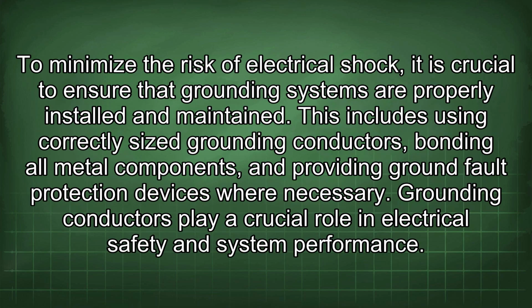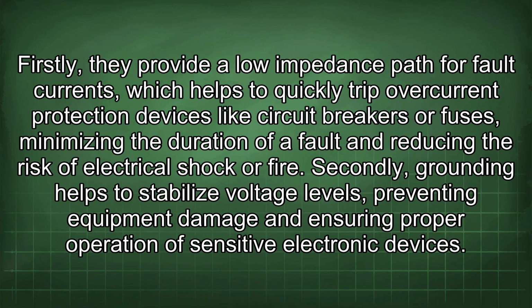To minimize the risk of electrical shock, it is crucial to ensure that grounding systems are properly installed and maintained. This includes using correctly sized grounding conductors, bonding all metal components, and providing ground fault protection devices where necessary. Grounding conductors play a crucial role in electrical safety and system performance. Firstly, they provide a low impedance path for fault currents, which helps to quickly trip overcurrent protection devices like circuit breakers or fuses, minimizing the duration of a fault and reducing the risk of electrical shock or fire.